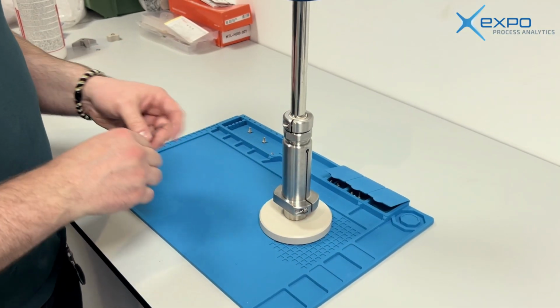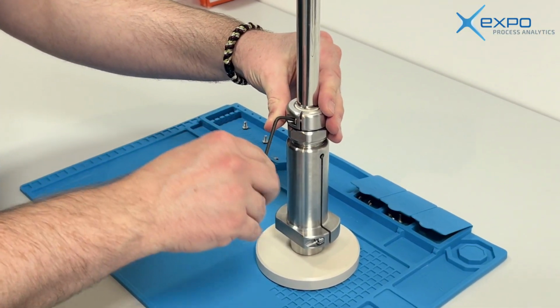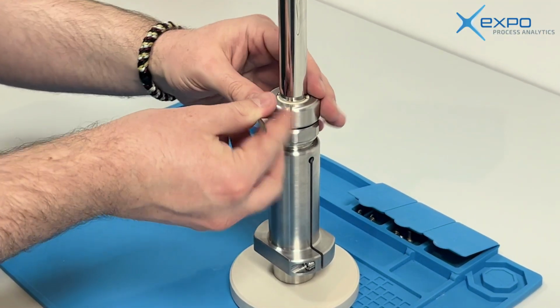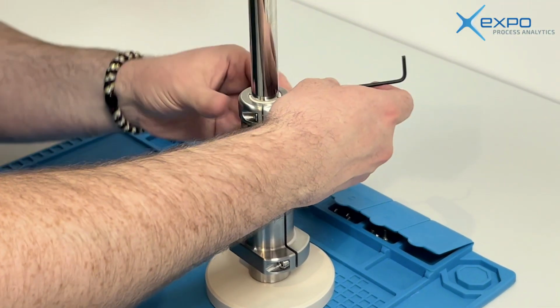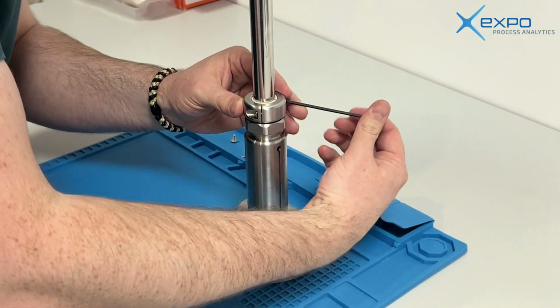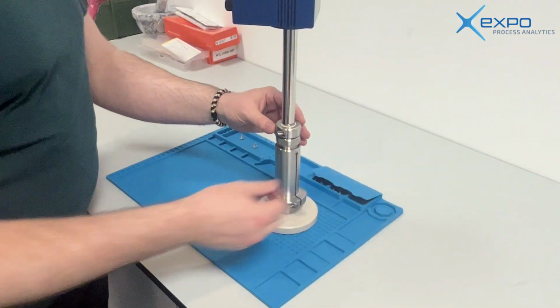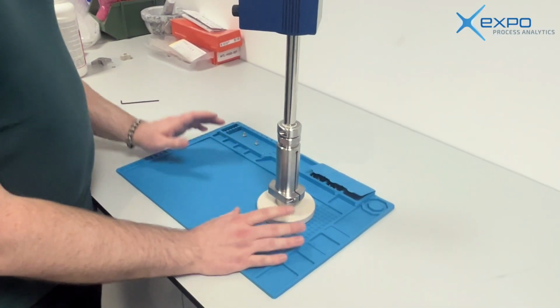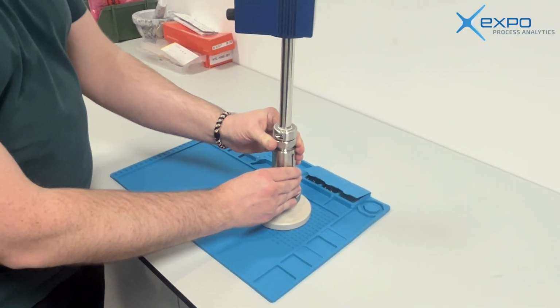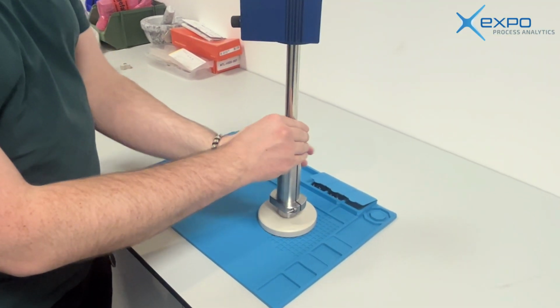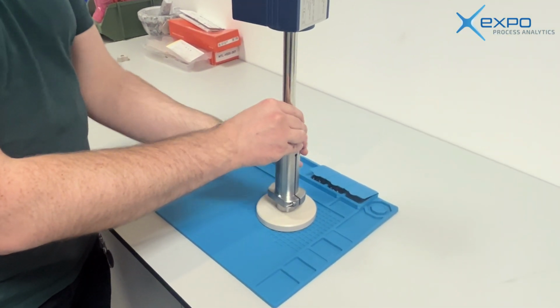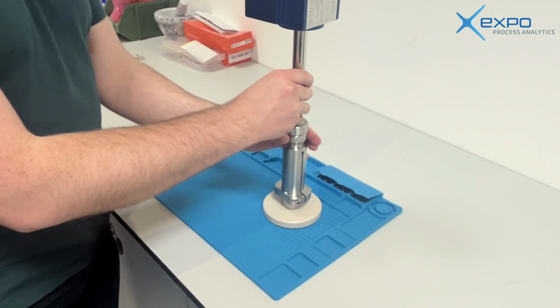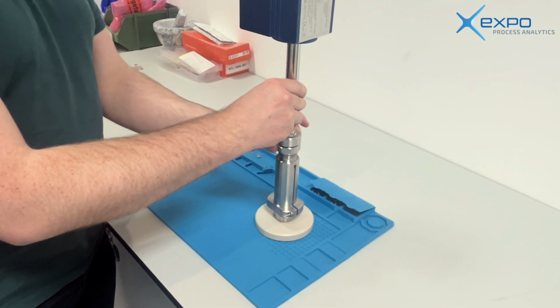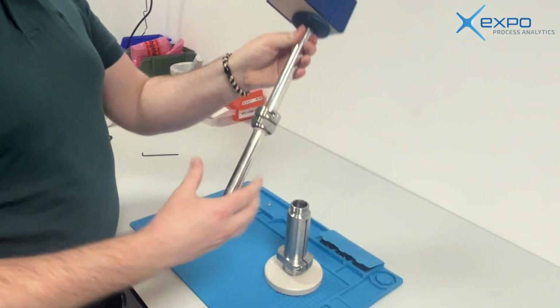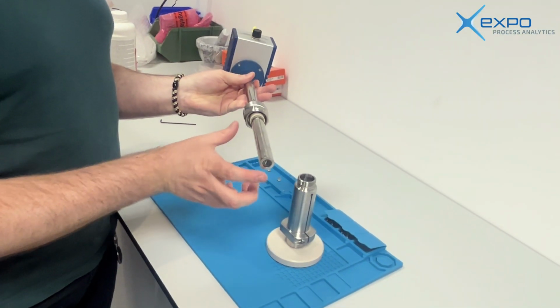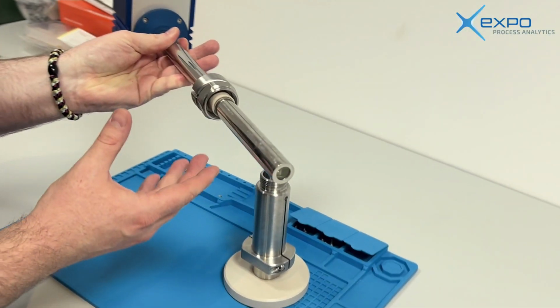At which point you will then tighten back up the clamp components on both sides evenly into predefined values, but I'm just tightening them loosely just for demonstration purposes. And at that stage, you can then again undo this fitting, or excuse me, undo the retaining nut. Remove the actual probe from the setting tool with sub-assembly in tow, and now you have the exact insertion depth that this device can be installed into the back of our device.